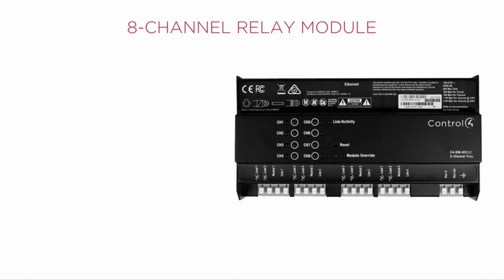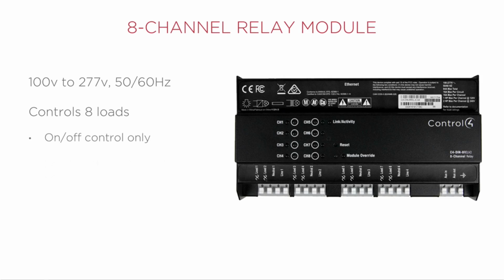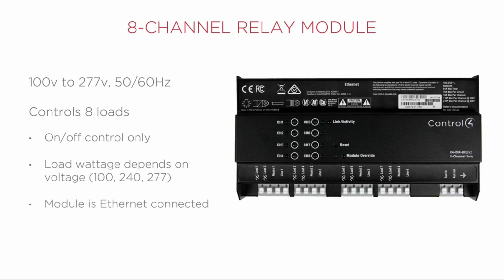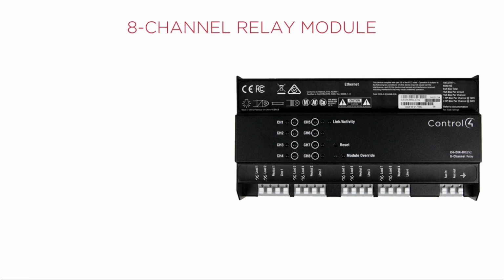The 8-channel relay module. Like the dimmer module, the 8-channel relay module can be used from 100 to 277 volts at 50 or 60 Hz. It can control 8 independently controlled loads. However, these loads can only be turned on or off. The load wattage depends on the voltage, 100, 240, or 277. The module is Ethernet connected, and those loads are controlled by keypads.